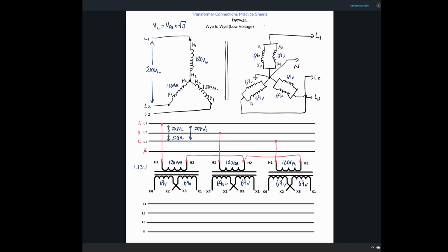This is the same diagram as we did before for the secondary, but now we've got different secondary voltages. Beautiful. Okay, so let's use that. I'm going to wait to do the line voltage because I want you to think about what the line voltage is. There's 69 volts from line to neutral, so what's the voltage from line to line on the output here? But let's do this wiring here first, and then we'll see if we can determine what that voltage is. Okay, so we are jumping X1 and X3 together, and X2 and X4. That creates that parallel connection that we've seen in all the other videos.